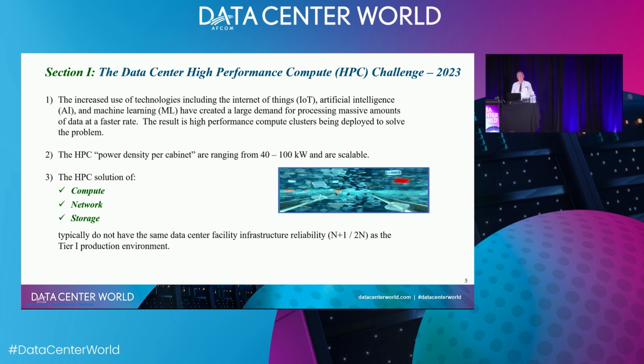Typically, in high-performance compute research, it does not require the same reliability or physical facility infrastructure reliability as other tier 1 applications. What does that mean? I could have a deployment of 10 racks at 90 kilowatts per cabinet, 900 kilowatts over 10 racks, but only needing 50 kVA of UPS power. It doesn't need any generator backup power, and the cooling can be N, because that research can go away. That's high performance compute research.